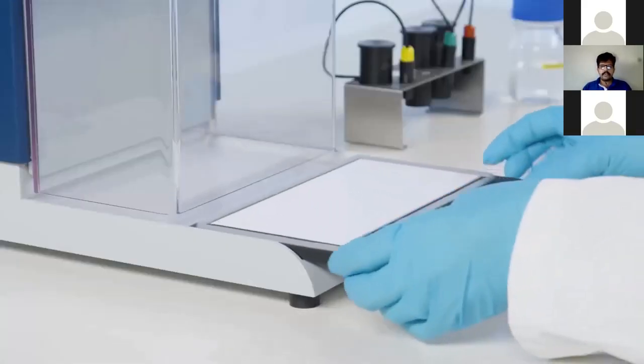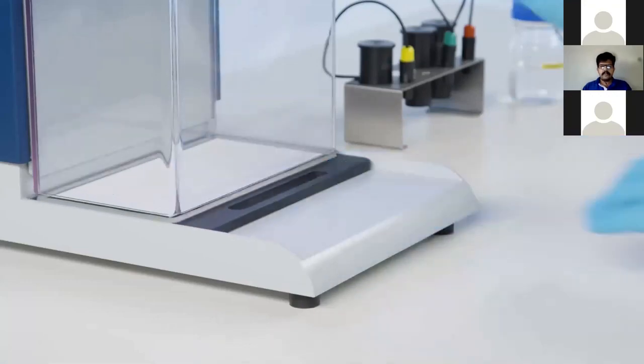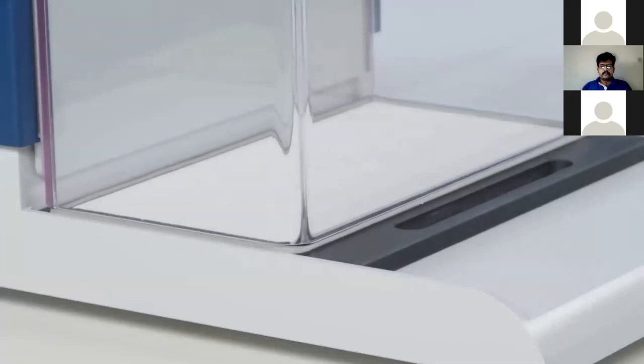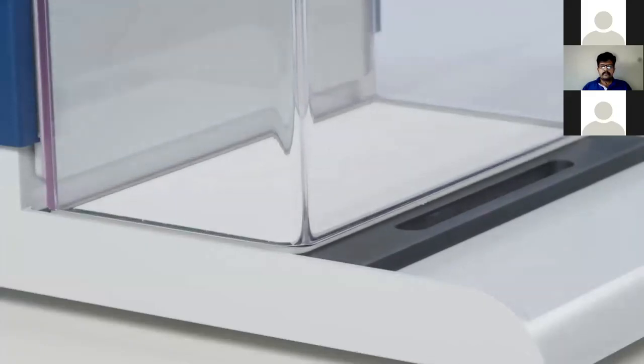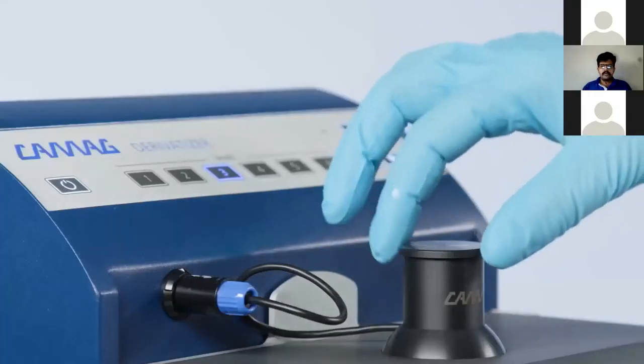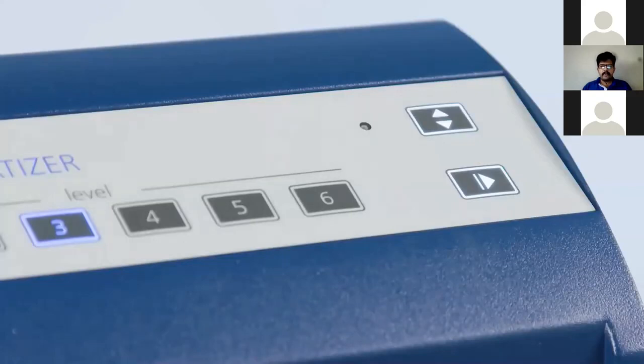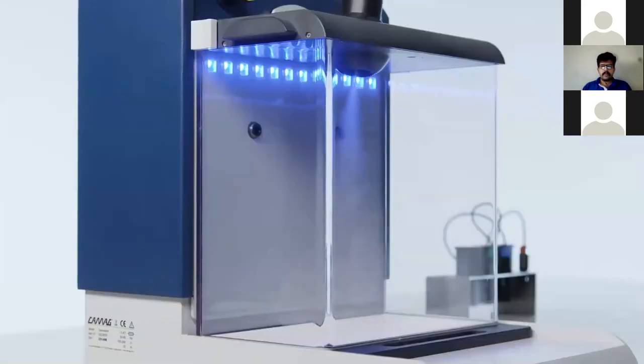The plate is placed inside. After positioning the plate, the hood is lowered and completely sealed to prevent the spraying reagent from leaking to the outside. Now what you do is add the recommended volume of 2 ml of your derivatizing reagent into the nozzle. In the dipping technique, you require around 200 ml, whereas here just 2 ml of reagent is required for a smaller plate. The spraying process is started by selecting the spraying level and activating the start button.